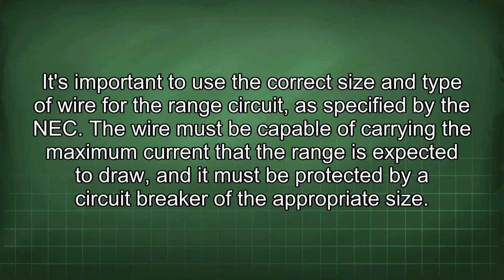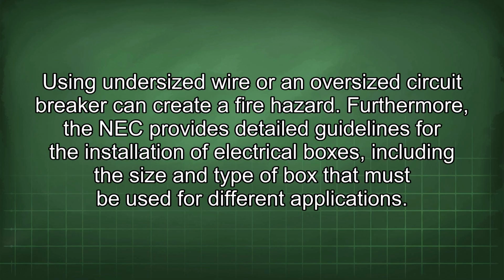It's important to use the correct size and type of wire for the range circuit, as specified by the NEC. The wire must be capable of carrying the maximum current that the range is expected to draw, and it must be protected by a circuit breaker of the appropriate size. Using undersized wire or an oversized circuit breaker can create a fire hazard.